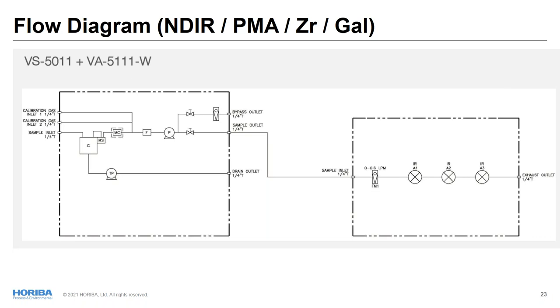All right, this is the flow diagram showing a wall mount sample system and the wall mount VA-5000, the general purpose version. As you can see, these NDIR, PMA, or zirconia galvanic O2 analyzers will be installed in this series. And if you are to measure NOx with one unit, then we're going to put the NOx converter inside so that the NOx converter will convert NO2 to NO.